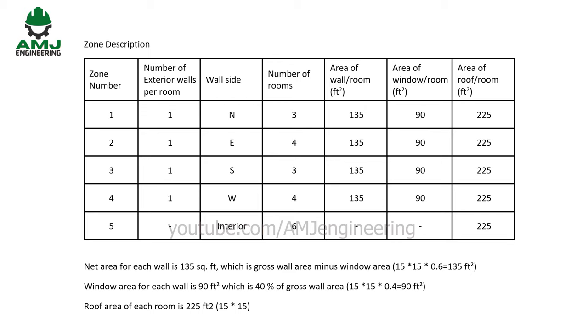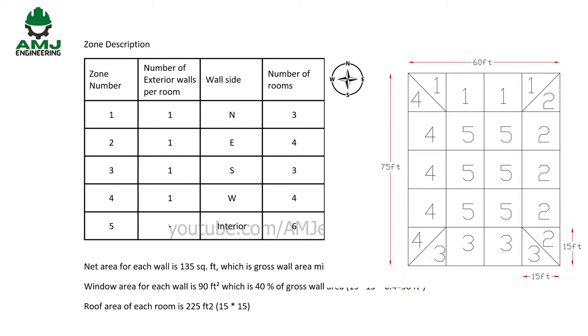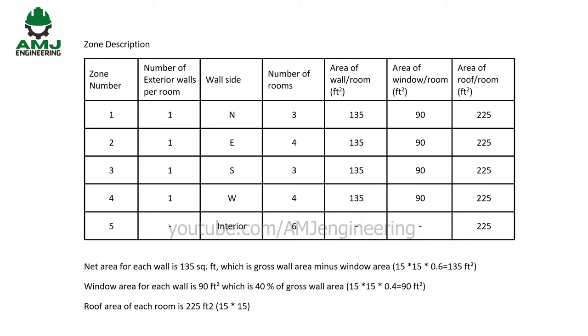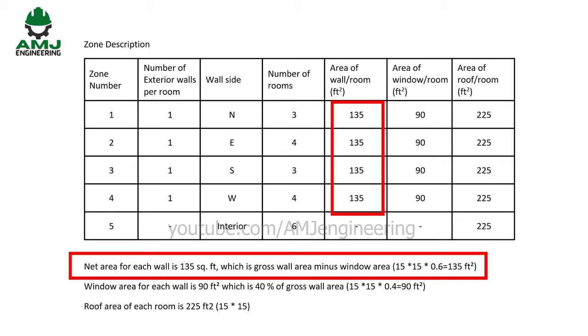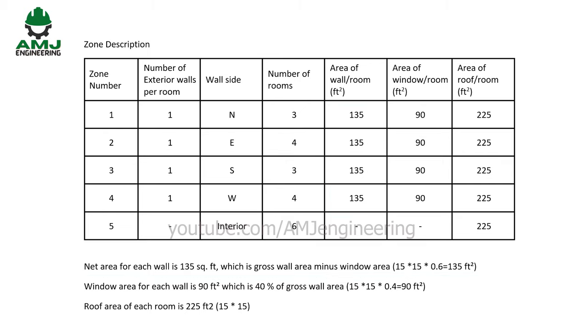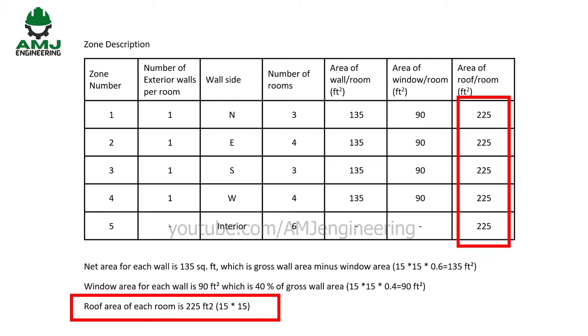Let's tabulate this data. The table includes: zone number, number of exterior walls per room (one in all peripheral rooms, zero in central rooms), wall facing direction, number of rooms per zone, and area of wall, window, and roof per room. Window area is 40% of gross wall area, giving 90 square feet per window. Net wall area is 135 square feet (gross minus window). Roof area per room equals floor area: 225 square feet.